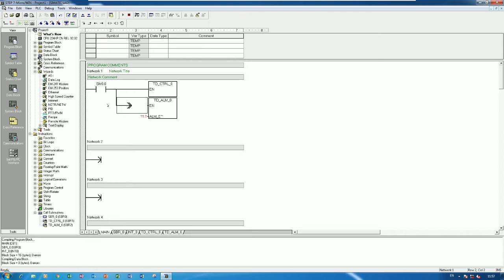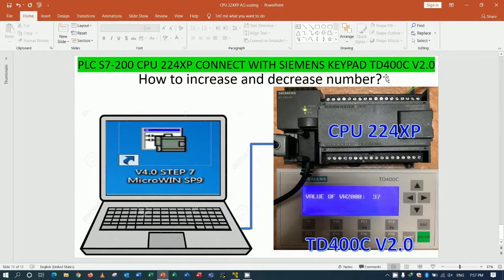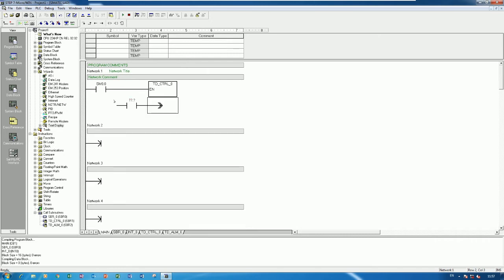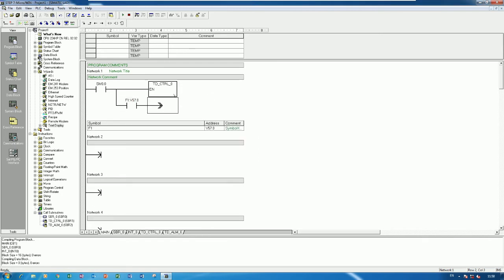I choose always ON. The alarm block does not need to be called since we are not using it. Here I will assign the keys: F1 to increase the value, F2 to decrease, and F3 to reset. For F1, right-click the address, choose Select Symbol, and choose F1. We need to use the positive edge contact, otherwise the value will count very fast when we hold the button.